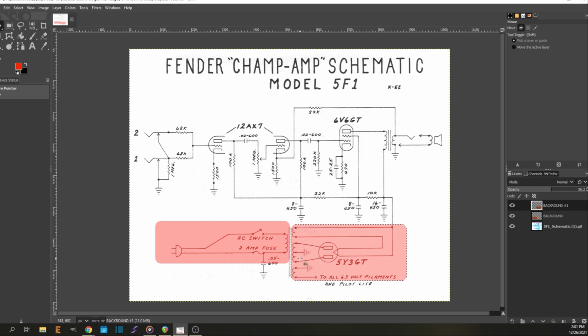All right, let's move up to this middle section right here. This is going to be our high voltage taps on the secondary side of the power transformer. So it takes this 120 and converts it up to about 325 volts to ground. Right here's ground, and then 325. If you measured across the two outer wires, you'd get 650 volts AC. This is center tap, so when it's referenced to ground, we get 325 on each side.